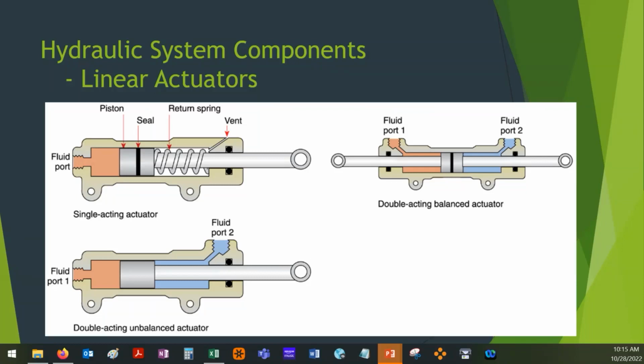So the fluid that comes in on the right here is only going to act on this small area above and below that shaft, or around, kind of a donut around the shaft. And so it's going to have a lot less force moving to the left than it is to the right. And so a balanced actuator, you can see, has the two shafts. The area that the fluid presses against is the same. Some of them will have the ability to connect something at both ends. Okay. You don't always connect both ends. Sometimes you only connect one end. Some of them will have one where there isn't a connection on the opposite end.